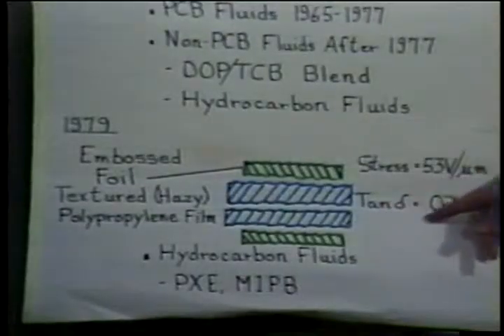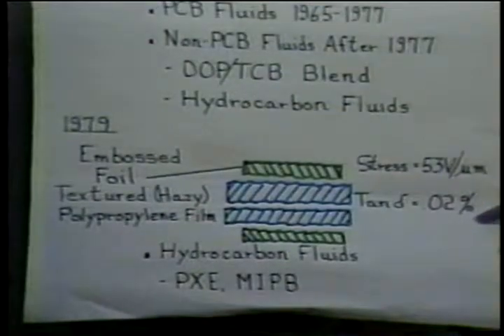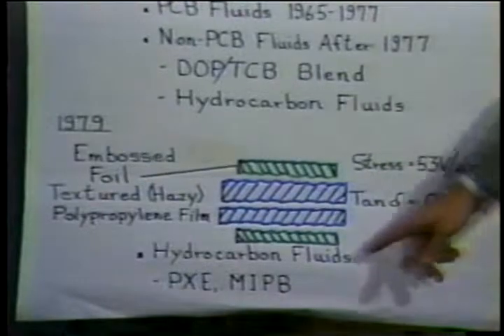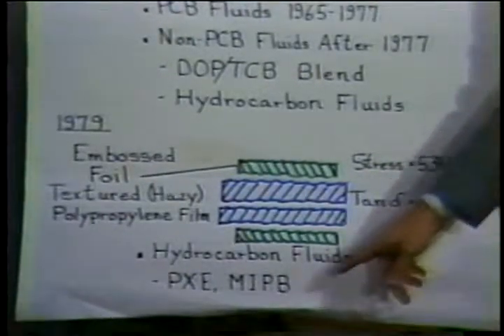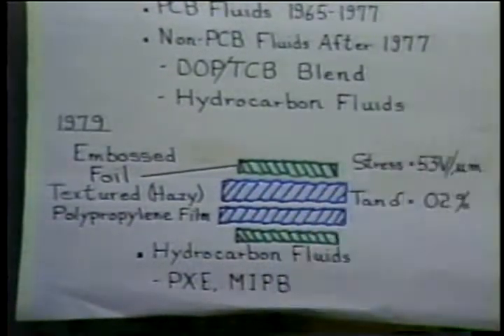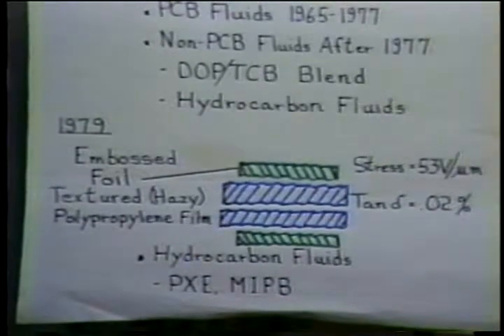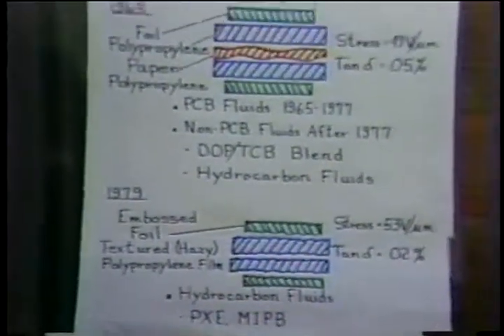The stress is approximately the same as that has been used in what is called an inverted sandwich construction, but the dissipation factor is even lower, 0.02%. This is very important because of the emphasis on energy savings in power utility applications. The fluid that is used in this design is a very important factor. Hydrocarbon fluids are used almost extensively. PXE and MIPB are the primary fluids.